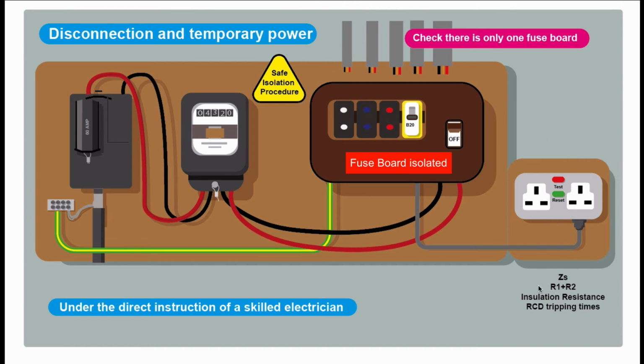We need to do our Zs, R1 plus R2s. That's going to be tiny. Insulation resistance again, there's a tiny little bit of cable, but got to do things right. And also your RCD tripping times. Make sure you've got all this recorded. People will be using this, so we need to treat it as a proper installation, even though it's only temporary. Test it and record it, and everything will be good. We've got our temporary supply, so everybody can crack on with some work.